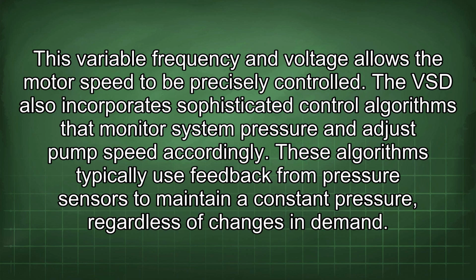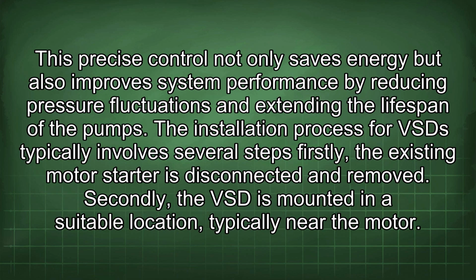The VSD also incorporates sophisticated control algorithms that monitor system pressure and adjust pump speed accordingly. These algorithms typically use feedback from pressure sensors to maintain a constant pressure, regardless of changes in demand. This precise control not only saves energy, but also improves system performance by reducing pressure fluctuations and extending the lifespan of the pumps. The installation process for VSD typically involves several steps.